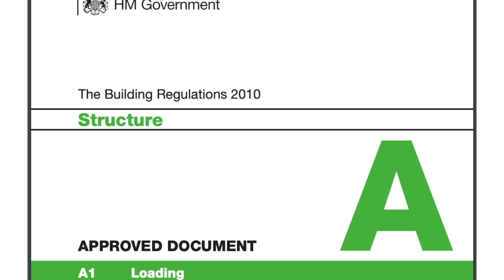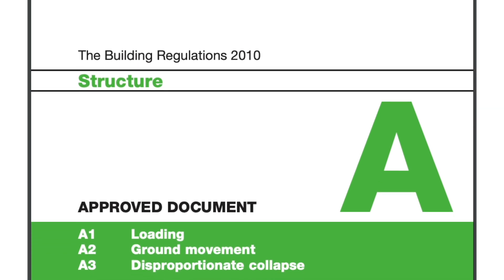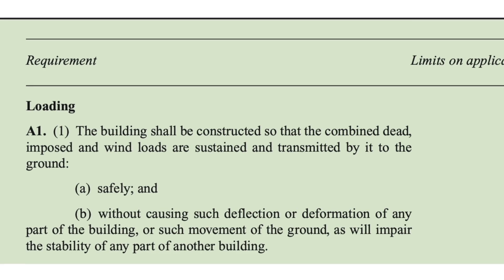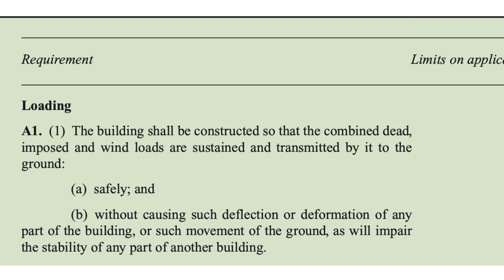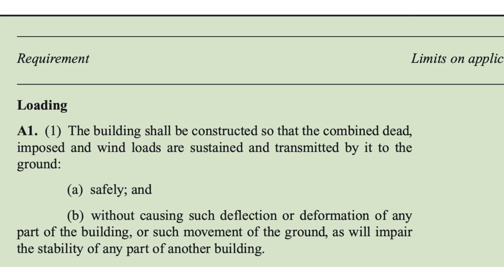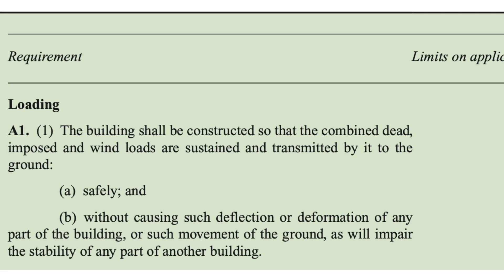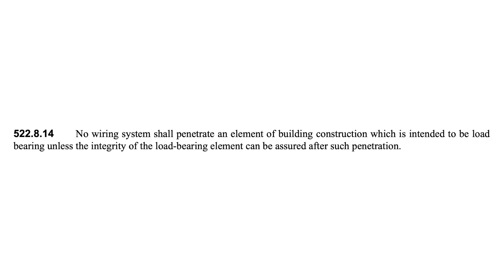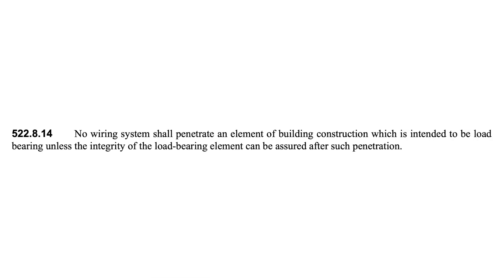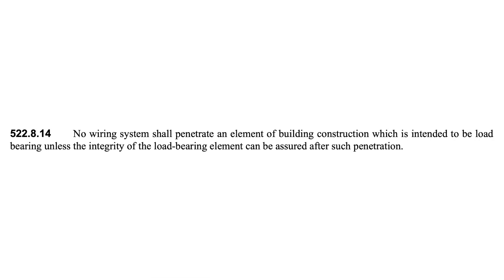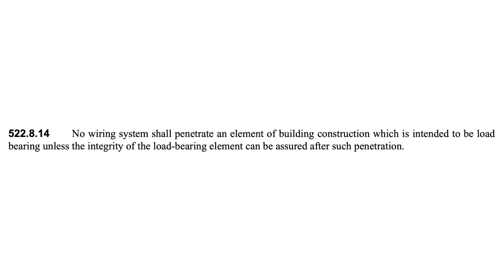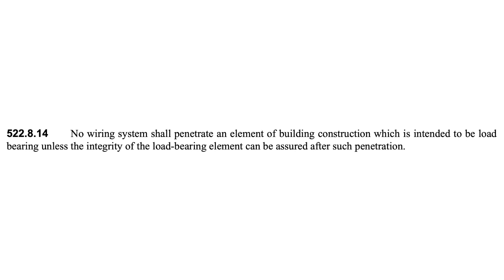What do the regs say about drilling through joists? Part A of the building regulations specifies that buildings shall be constructed so that loads are sustained and transmitted to the ground: a. safely and b. without causing such deflection or deformation of any part of the building or disproportionate collapse. Furthermore, Regulation 522.8.14 of BS7671 states that no wiring system should penetrate an element of construction that is intended to be load bearing unless the load bearing ability of the element remains satisfactory after such penetration.